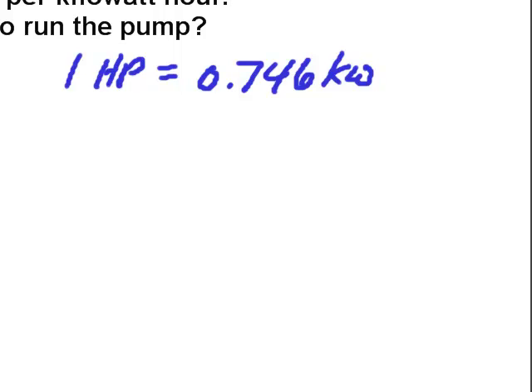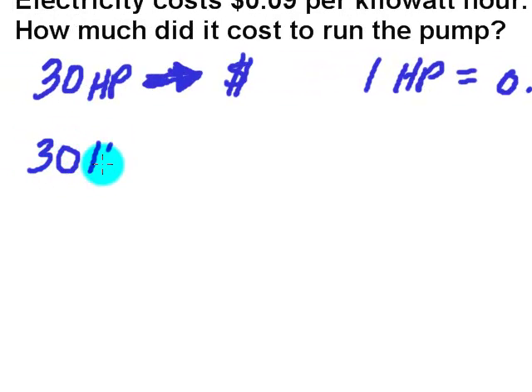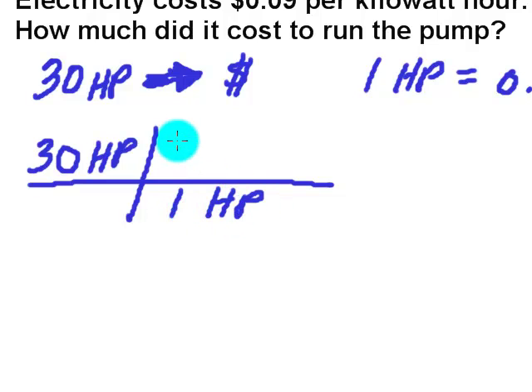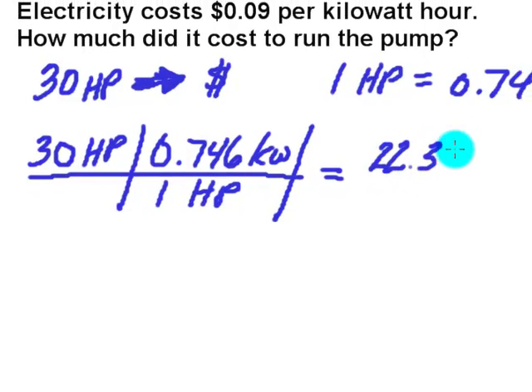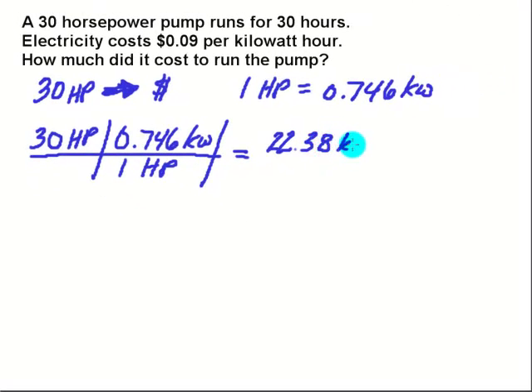The first thing that we have to do is convert horsepower into kilowatts. So I've got my 30 horsepower, drawing the backbone of my track here. And for every one horsepower there are 0.746 kilowatts. So if I make that conversion, I find that my pump didn't really use 30 horsepower. What it used was 30 times .746 or 22.38 kilowatts.